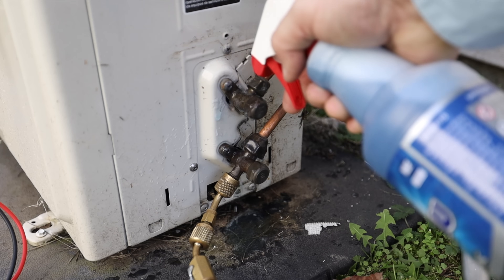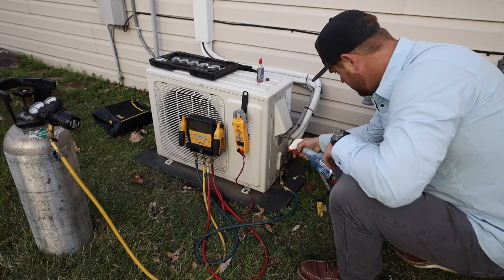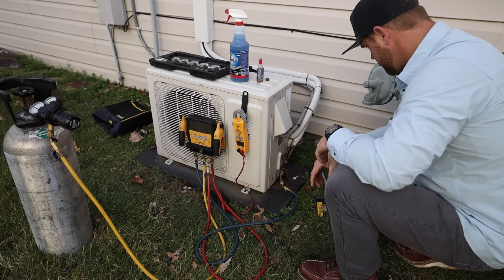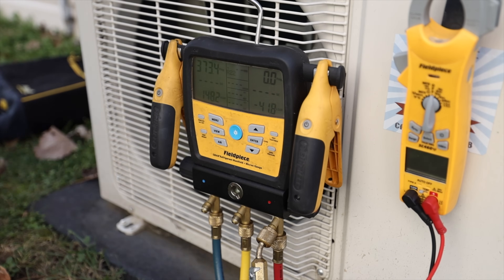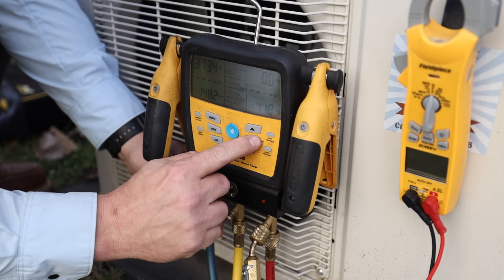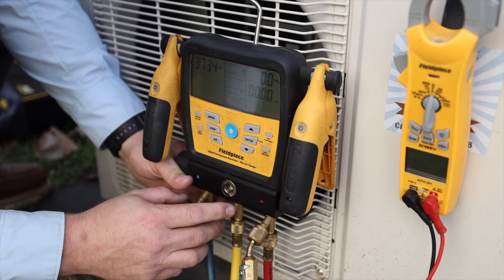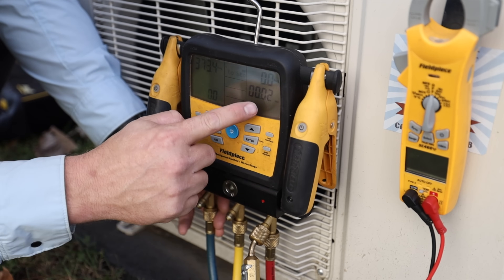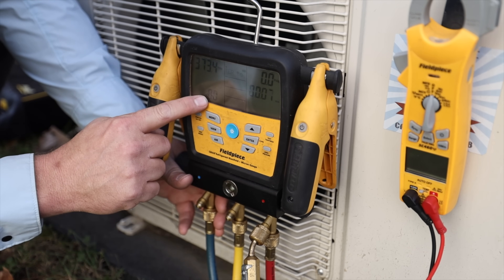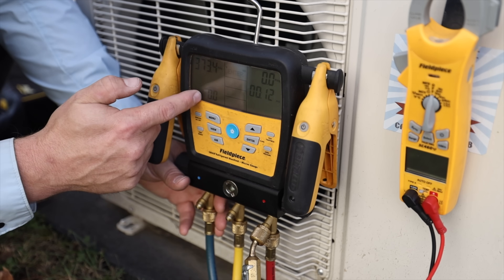I'll go ahead and test the bottom one as well and the cap, just to make sure everything is leak free. So far I think we're in good shape. Everything is looking pretty good. I'm going to go ahead and start a pressure test on this Fieldpiece SMAN — it's built into the gauge. You can do a test for tightness: hold that down, press enter, and it starts timing and checks the pressure difference. We'll let that run for about 10 minutes and make sure we don't have a significant drop in pressure.